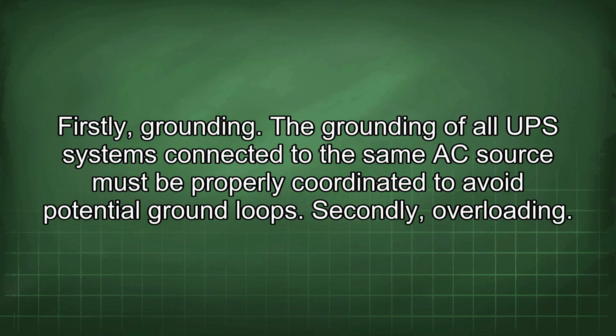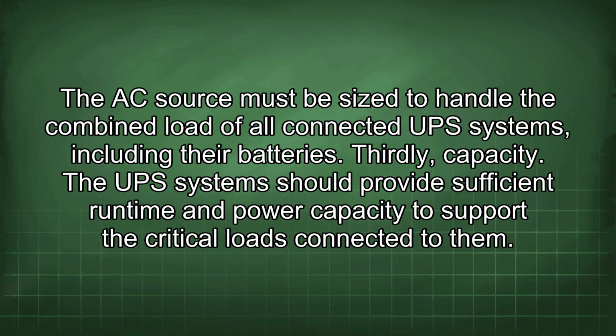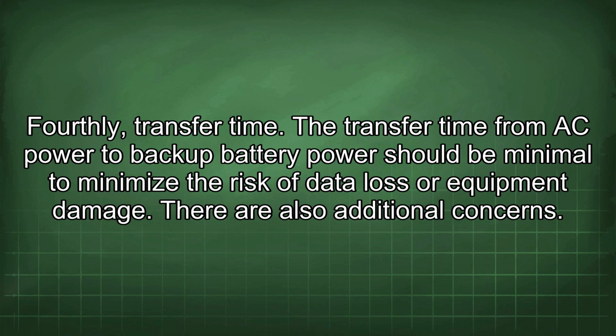Firstly, grounding. The grounding of all UPS systems connected to the same AC source must be properly coordinated to avoid potential ground loops. Secondly, overloading. The AC source must be sized to handle the combined load of all connected UPS systems, including their batteries. Thirdly, capacity. The UPS system should provide sufficient runtime and power capacity to support the critical loads connected to them. Fourthly, transfer time. The transfer time from AC power to backup battery power should be minimal to minimize the risk of data loss or equipment damage.